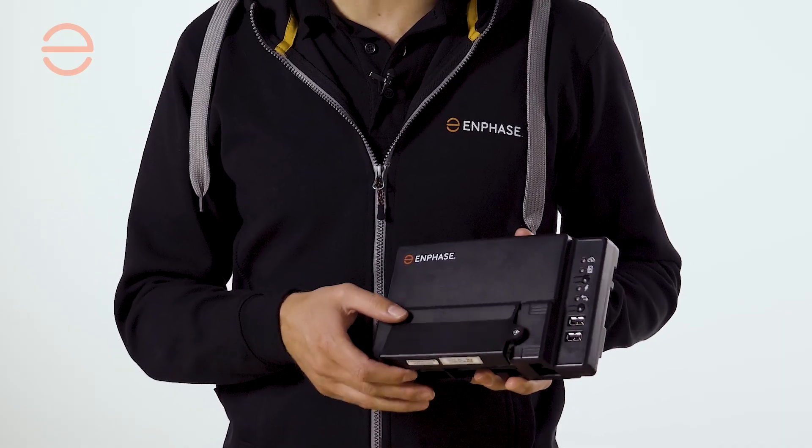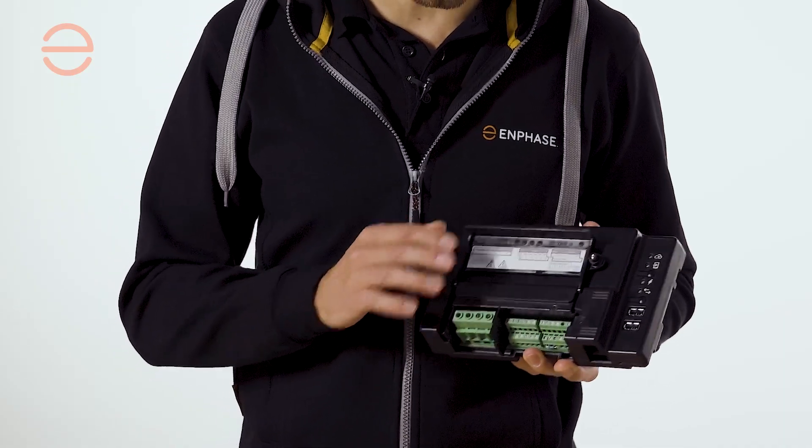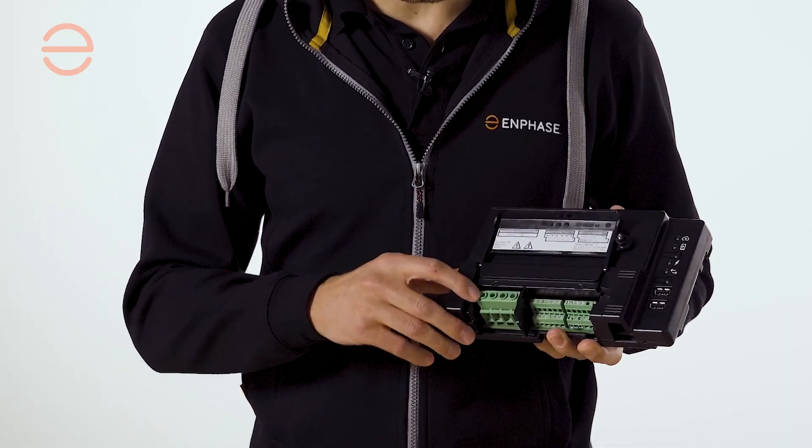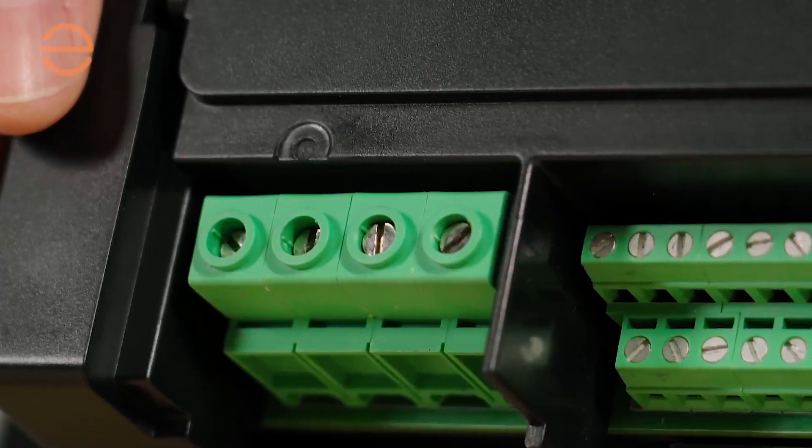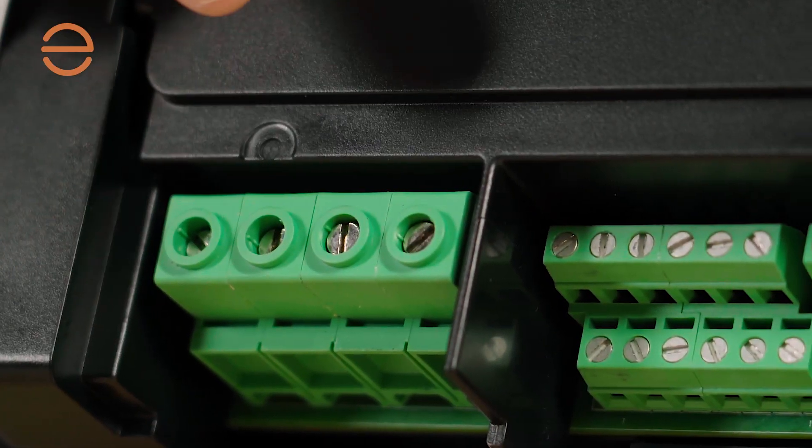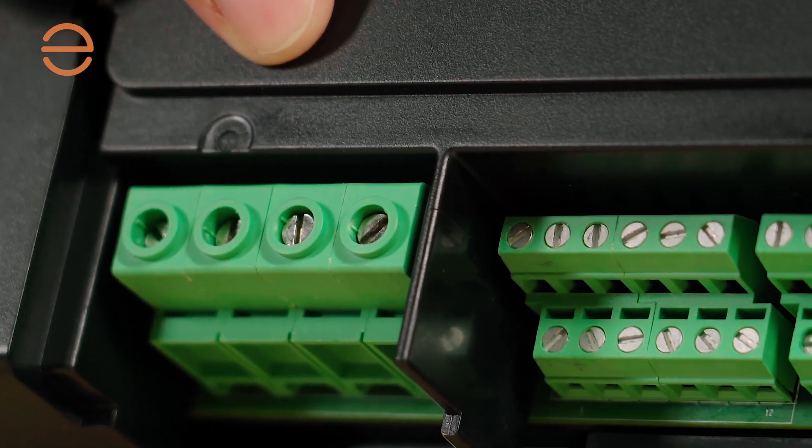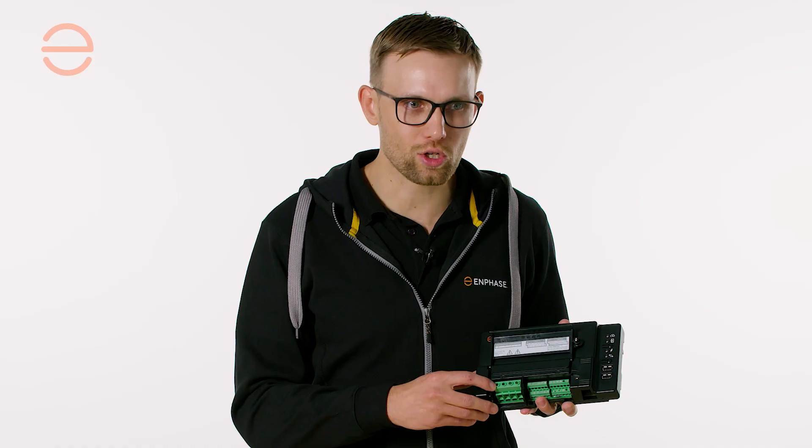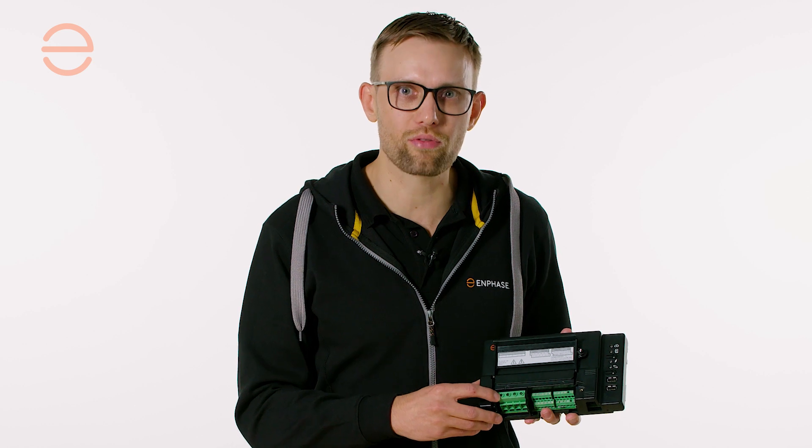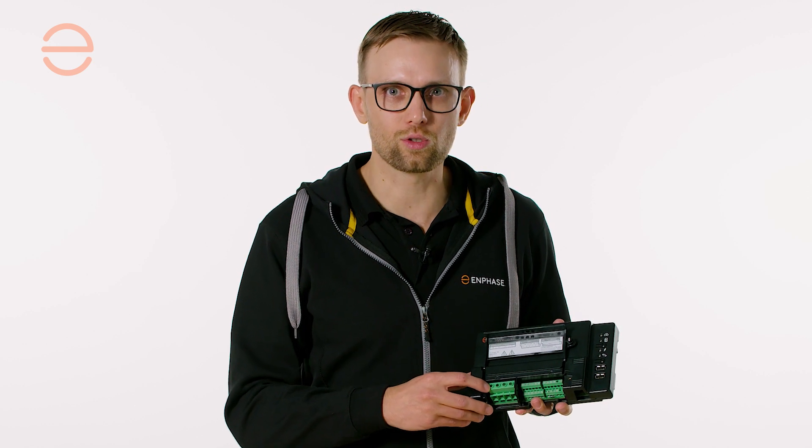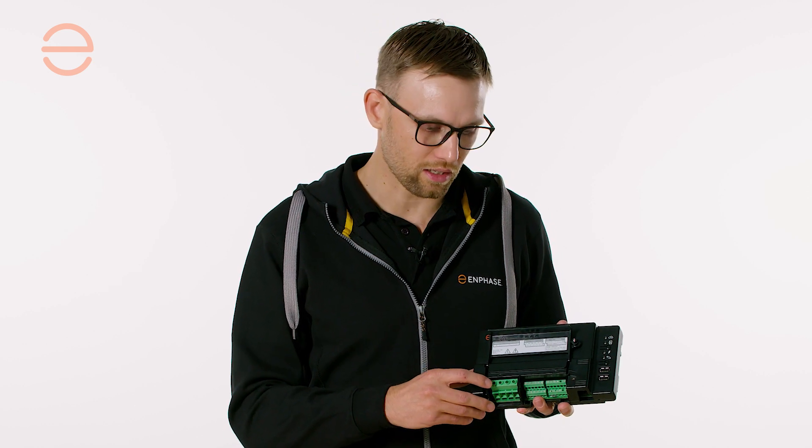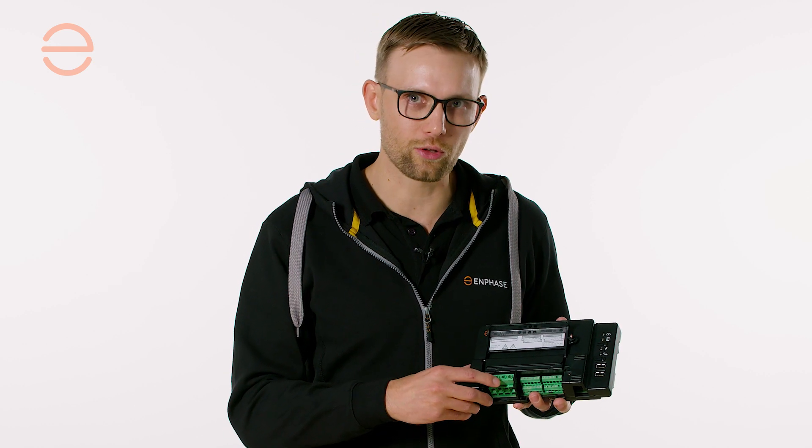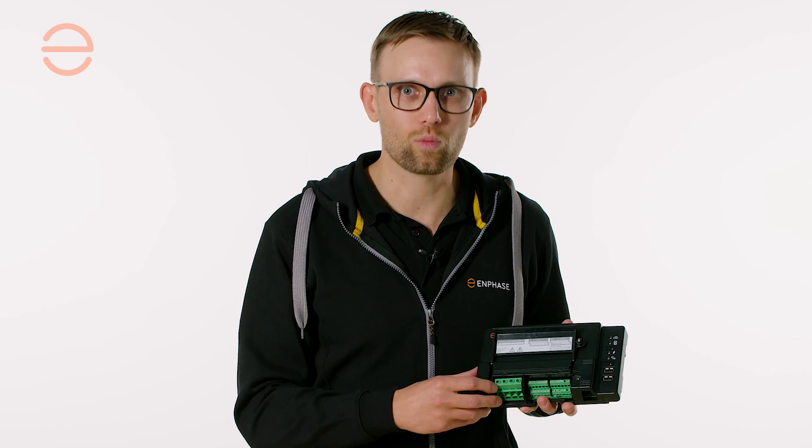On the iQ Gateway, you have your power connections on the left, with the neutral always being the leftmost side. Make sure in three-phase configurations that you don't accidentally go L1, L2, L3, neutral, because that will damage the device.